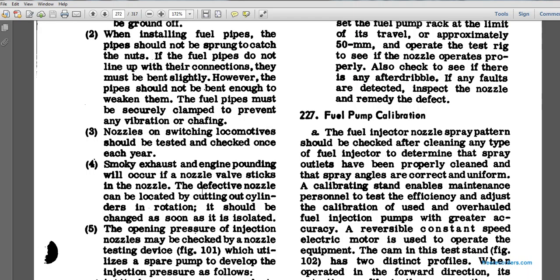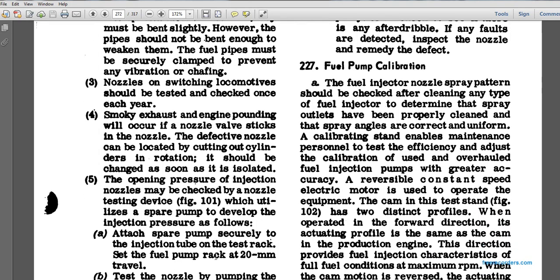Smoky exhaust and engine pounding will occur if a nozzle valve sticks in the nozzle. The defective nozzle can be located by cutting out the cylinder in rotation. It should be changed as soon as it is isolated. The opening pressure of injection may be checked by a nozzle testing device, which also utilizes a spare pump to develop an injection pressure, as follows.